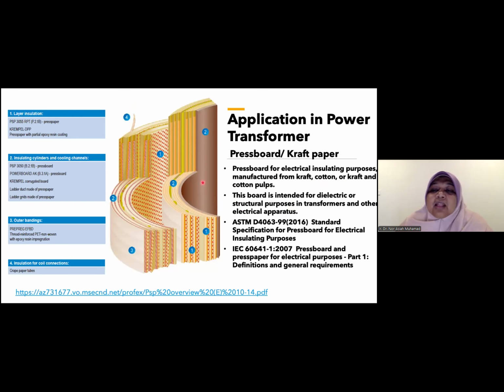Besides the dielectric purpose, it also has a structural purpose to hold the winding in its place, because a shift of the winding will give different electrical strength. So it will produce high spots of electrical field. To maintain the winding in the proper structure, we need a good solid insulating material.